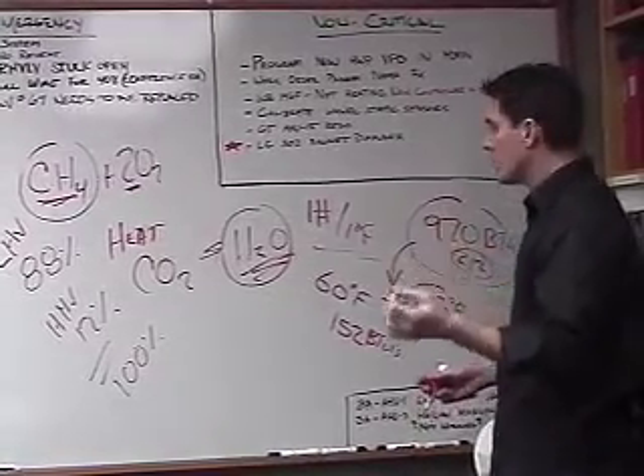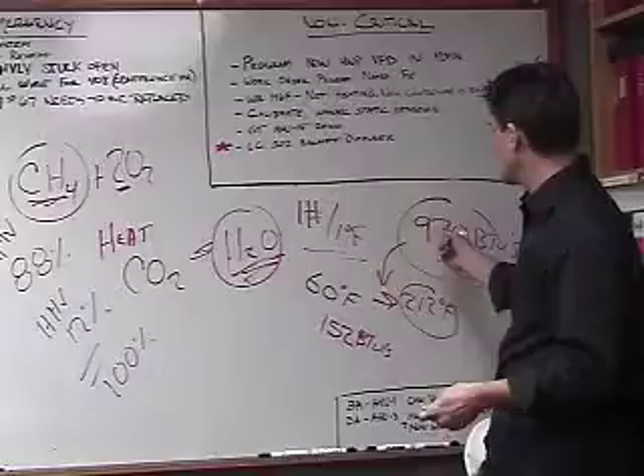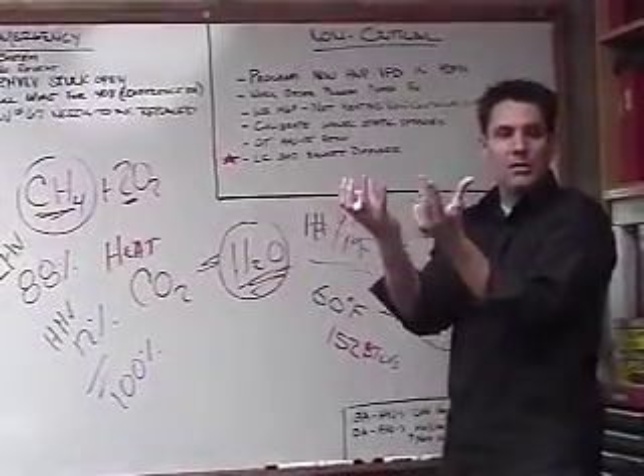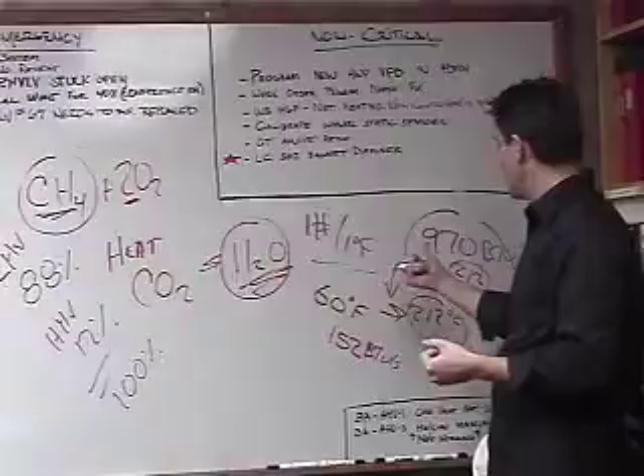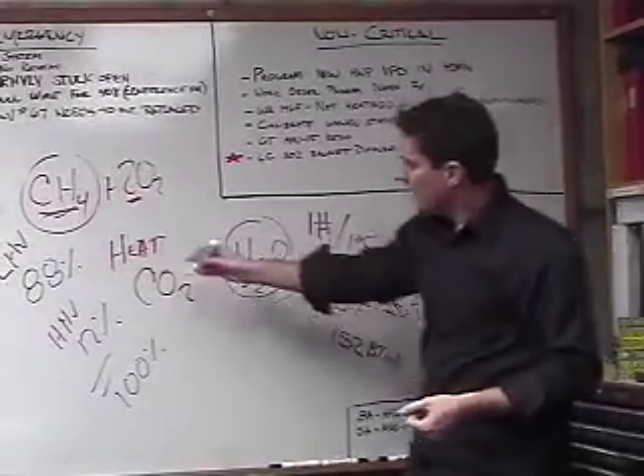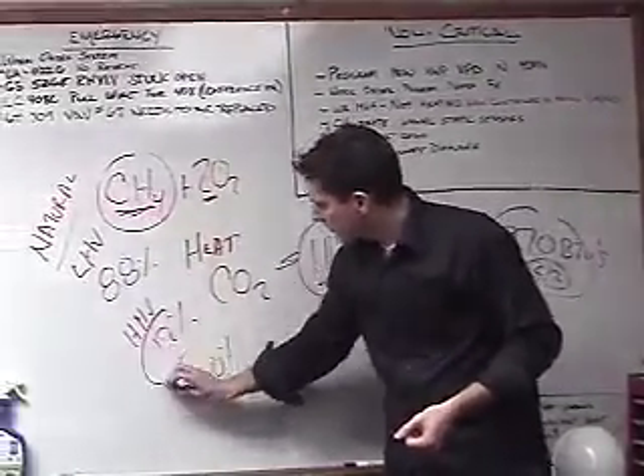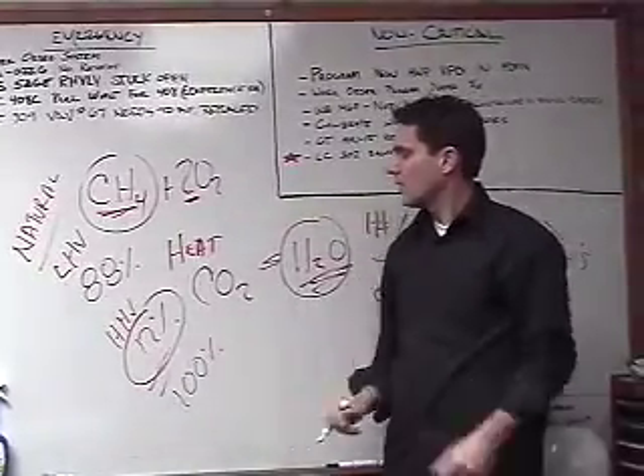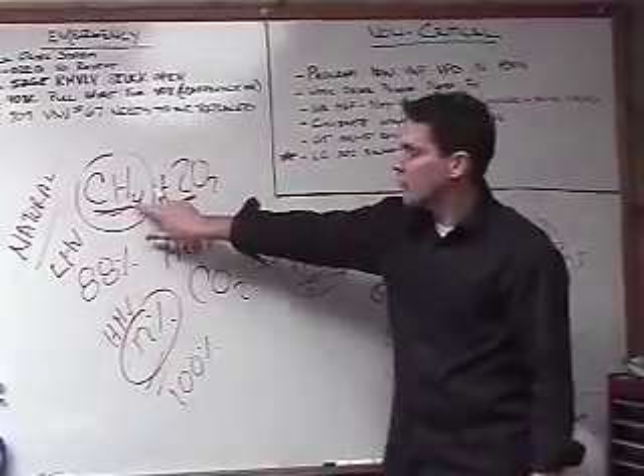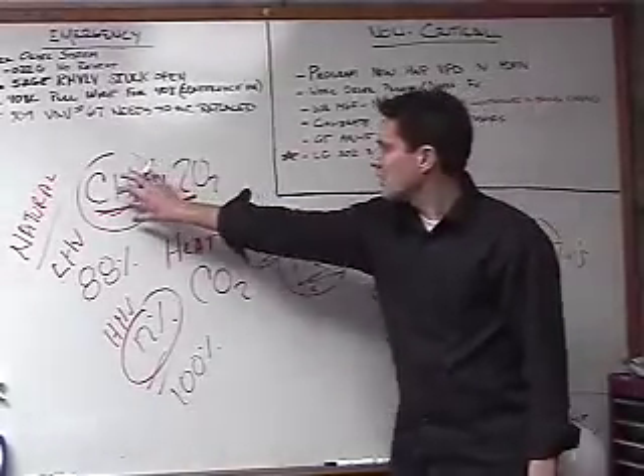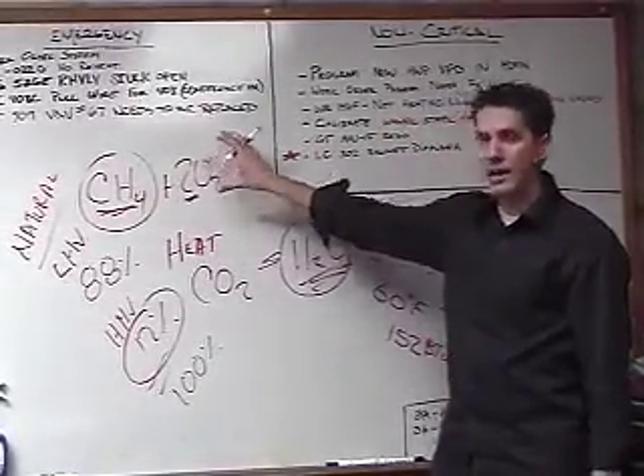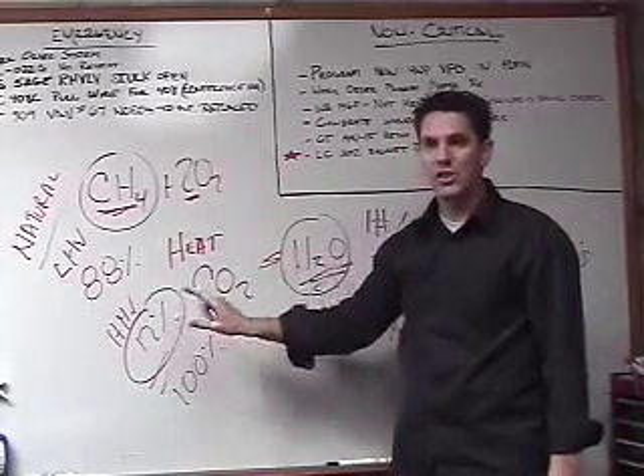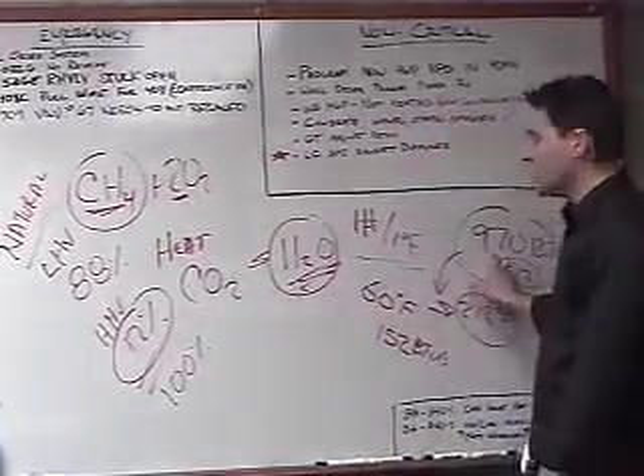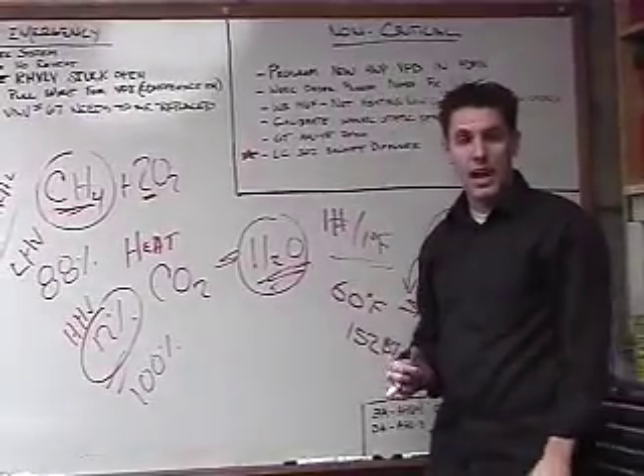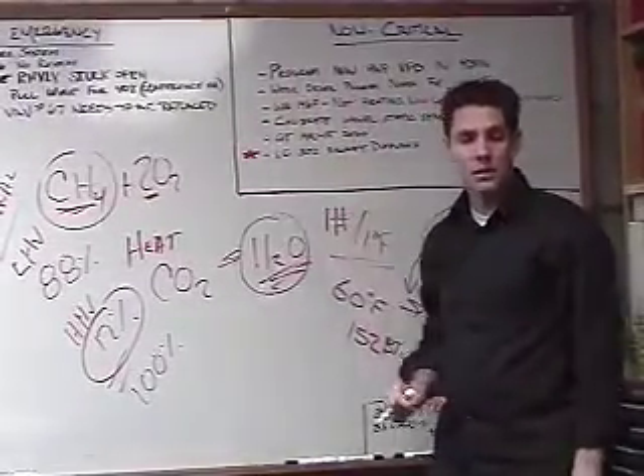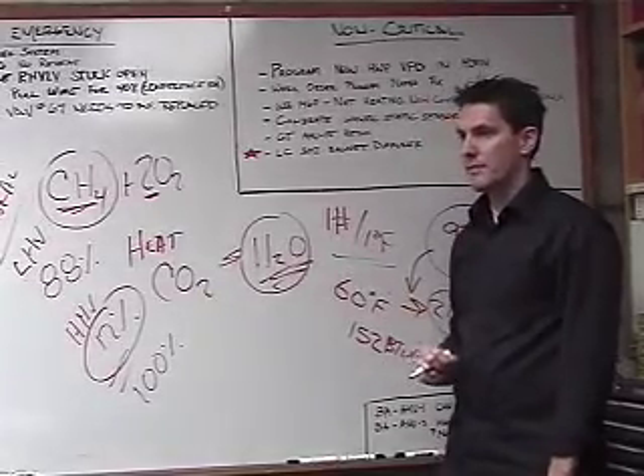So what a condensing boiler is doing, or what any boiler will do if we start to condense, is taking that steam and turning it back into a liquid, and as it condenses out, it gives up a lot of BTUs. When we look at natural gas, that steam is holding about 12% of our energy, because of the CH4. All these hydrogens are mixing with the oxygen molecules, we're creating H2O, and 12% of our energy is just going up in the steam, with this BTU locked in, and it's going out into the atmosphere. It condenses once it gets outside, it's condensing somewhere, but we're not capturing this energy.